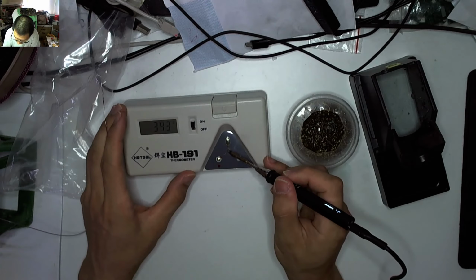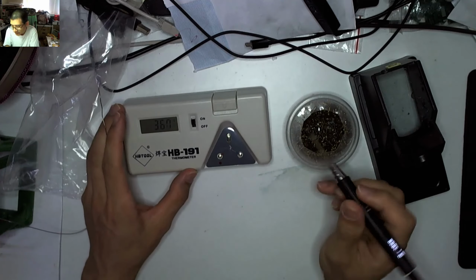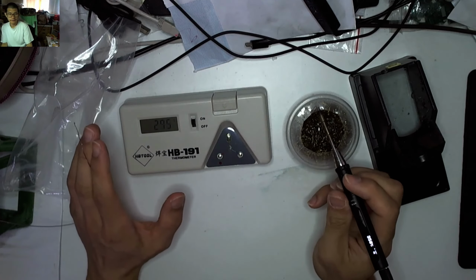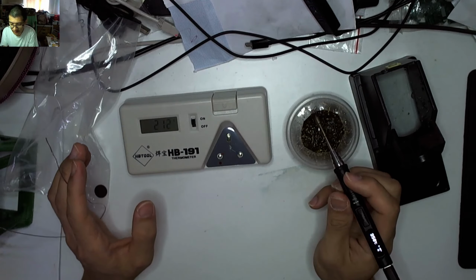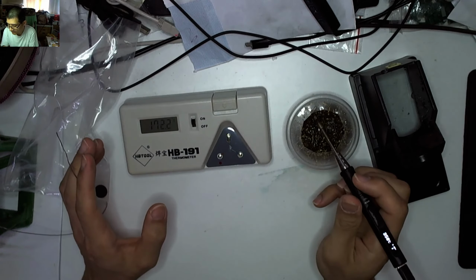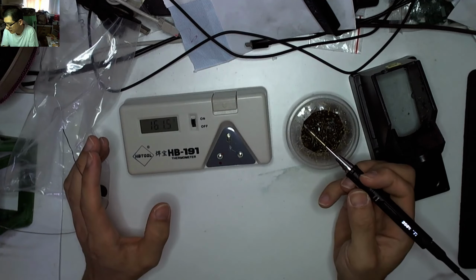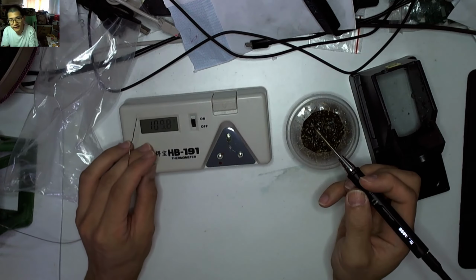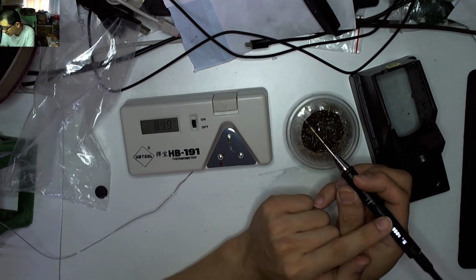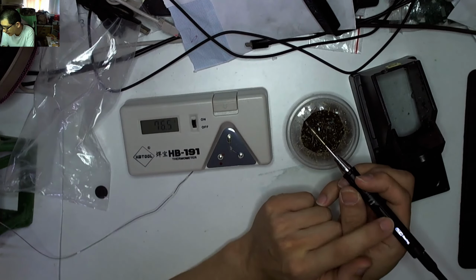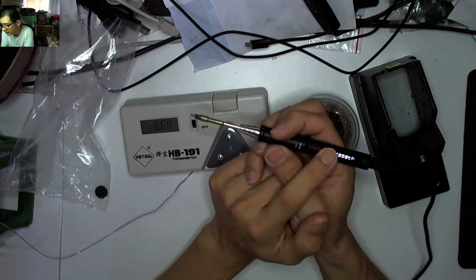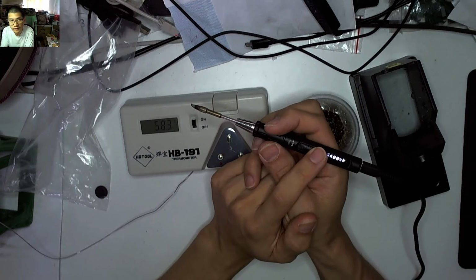And so you want to just be touching it, but you don't want to be pushing it too hard. And look at that. I'm now actually quite a bit over at 368. So before we were 9 degrees off at 300. So 9 times 5 is 45. 45 plus 350, it should be reading around 390 if it was linear, so it's not. So we're only about, what, 18 degrees over, so it's double that. So let's have a look at if we go up even further. Let me just reset the temperature to 400 degrees.